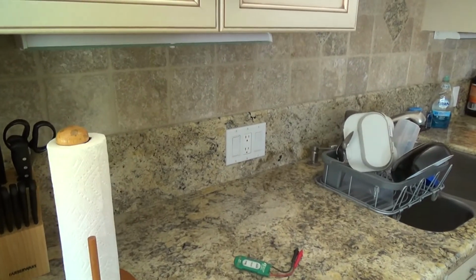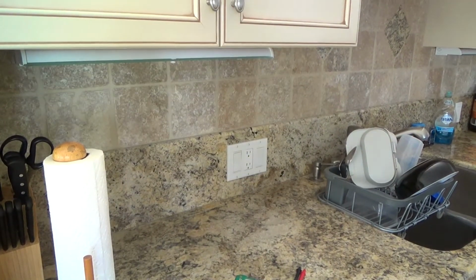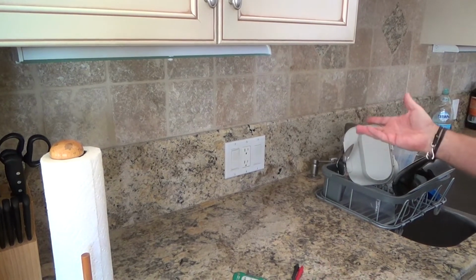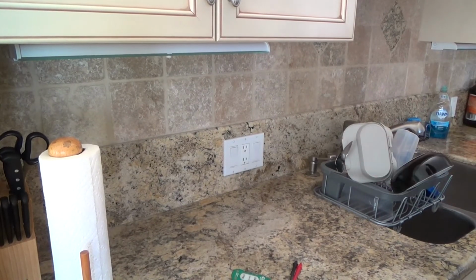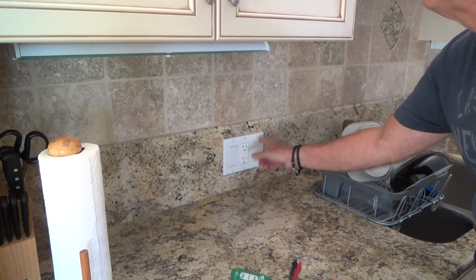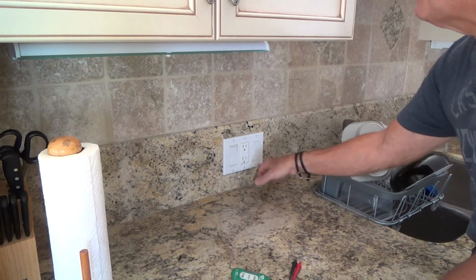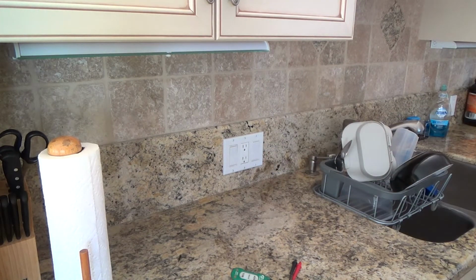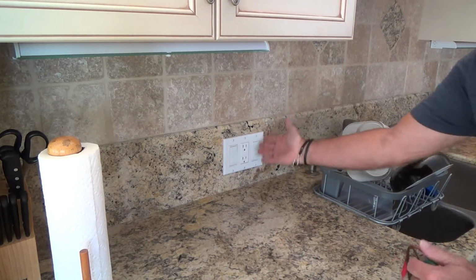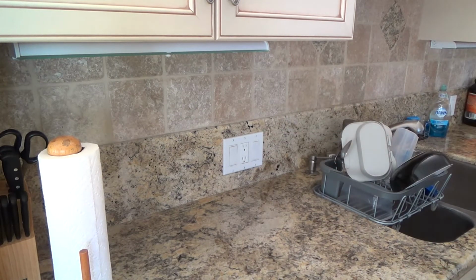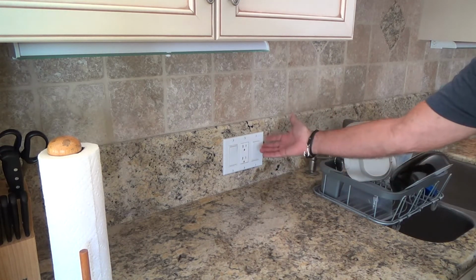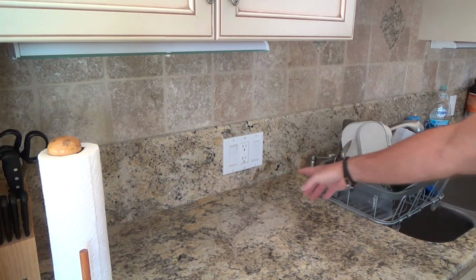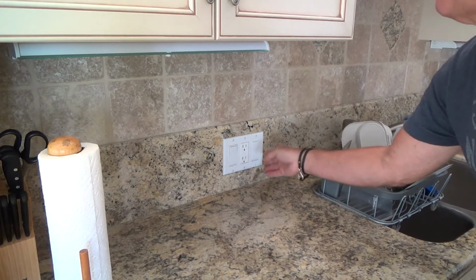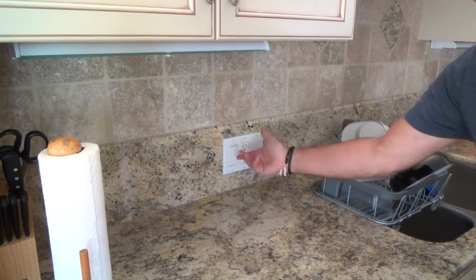You want to make sure you check things, because what would have happened if I didn't do that first? If I made the assumption it's working, turn the breaker off, come back up here, hit the switch, and sure enough the light's off—but what if the light bulb was burned out? The light's off and I think I've got the right breaker, so I start pulling this apart because I thought the light was off since the switch says it's off, and I find out there's power in here.